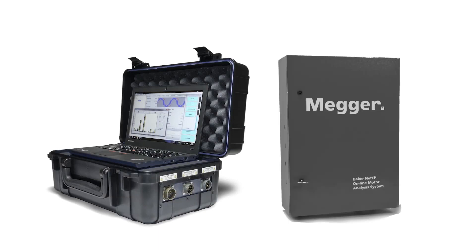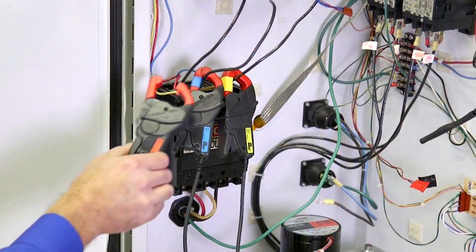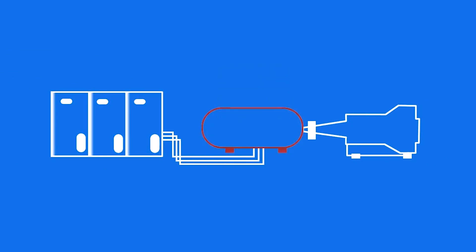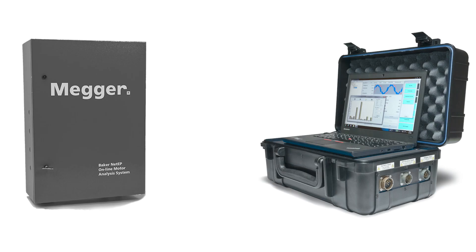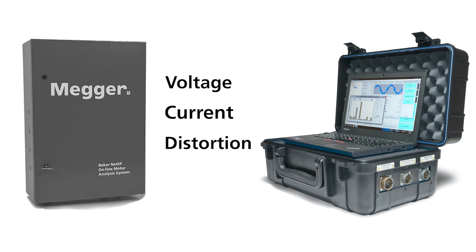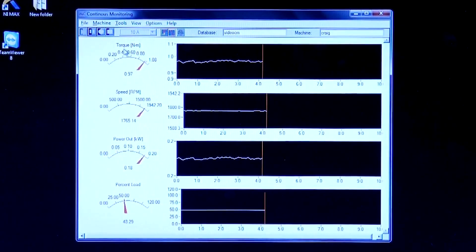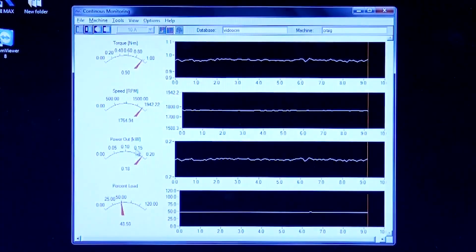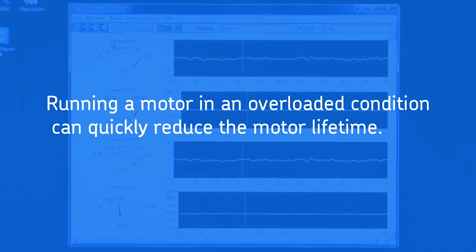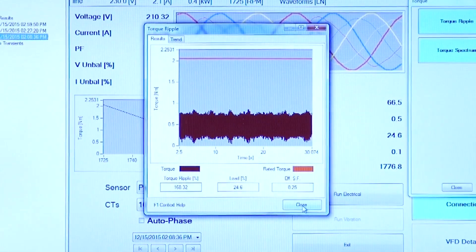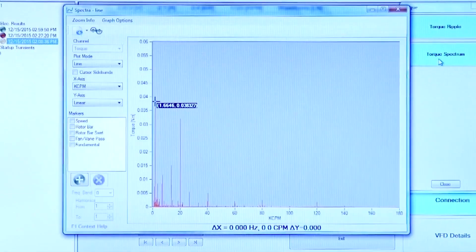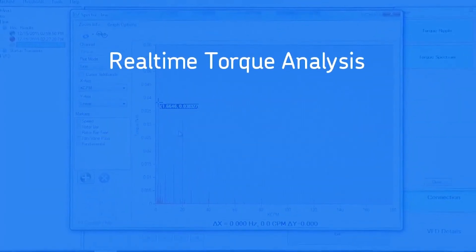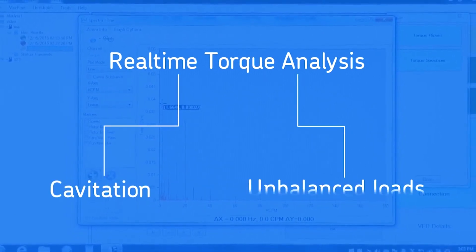Let's look at the motor operating point using Baker Dynamic Motor Analyzers. The operating point is measured while the motor or machine is energized and operated, with connections made to measure motor voltages and currents. The EXP 4000 and NET EP analyze incoming power, including voltage and current levels, distortion, and balance. Motor performance is analyzed using motor speed, torque, load ratings, and efficiency. Running a motor in an overloaded condition can quickly reduce motor lifetime. Baker Instruments Dynamic Motor Analyzers allow you to look at load torque in real time to find even temporary overload conditions or machine faults such as cavitation or unbalanced loads.